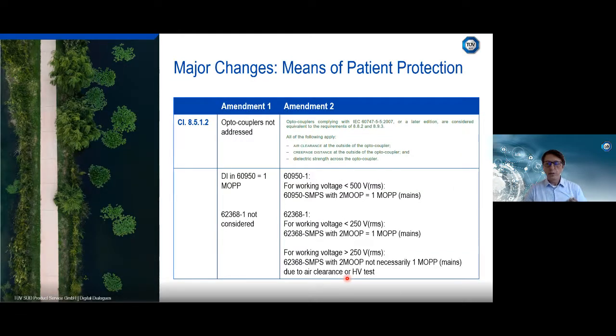When we have a look at the patient protection, there were also some changes. First, we now talk about optocouplers, where we have a clear reference in Amendment 2 that optocouplers shall comply with IEC 60747-5-5. And when they comply with these requirements, they also comply with the requirements of the basic standard 60601-1, especially with respect to air clearance, creepage distance, and dielectric strength test. A new reference implemented for Amendment 2 is the standard 62368-1. This is about IT equipment. In Amendment 1, this standard was not referenced, and we only had a reference for 60950. So IT equipment formally could only be used when it complied with 60950 in the past.